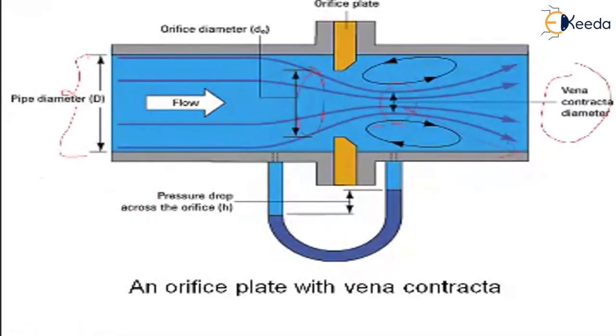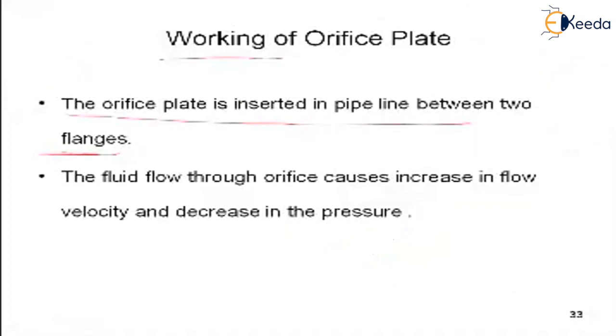The orifice plate is inserted in a pipeline between two flanges — flange one and flange two — and the orifice plate is located between them. The fluid flowing through the orifice causes an increase in flow velocity and a decrease in pressure. At one position beyond the orifice plate, the velocity is maximum and the pressure is minimum.